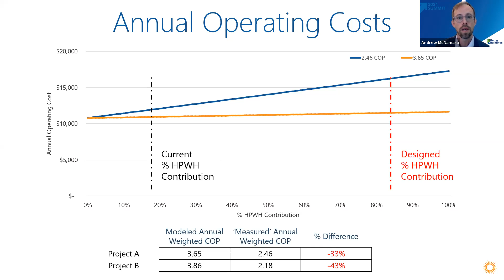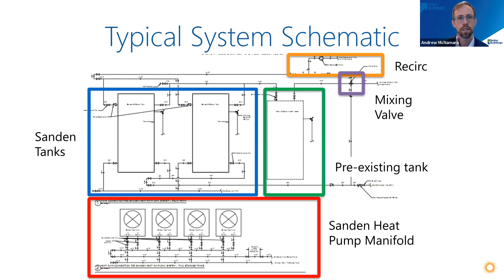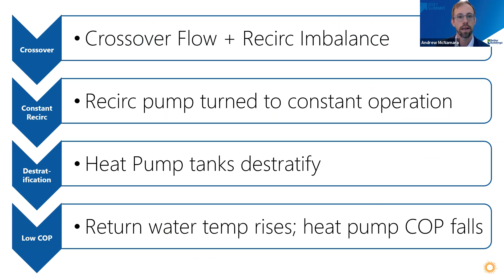Moving on to the next slide, you can see a typical system schematic for our Sanden systems. I won't get into detail here today, but the next slide shows an overview of distribution issues in a flowchart form: how existing property issues of crossover flow and recirc imbalance led to needing to operate the recirc pump constantly to avoid complaints. That was the maintenance staff response, which led to the heat pump tanks destratifying, which led in turn to higher return water temperature, a lower COP, and higher operating costs.